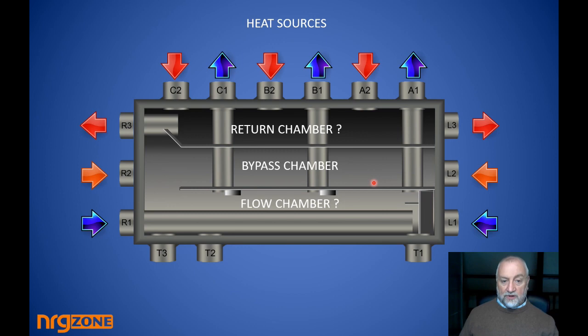So the flow chamber, instead of being a physical geographical point on the unit, is actually where the heat is introduced into and the heat is taken away from to deliver heat to the zones. The return chamber is where you would take the heat away from back to your boiler, but that you bring your returns back into. So here you can see we're reversing the whole scenario here. We're now saying that what was the flow chamber, question mark, is now actually the return chamber. What was the return chamber on the top, question mark, is now the flow chamber, where you're delivering flow into and taking it away from.